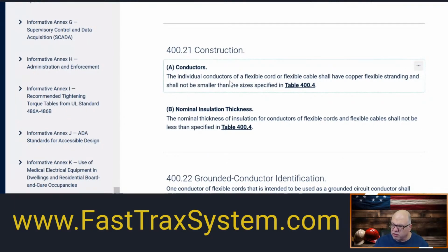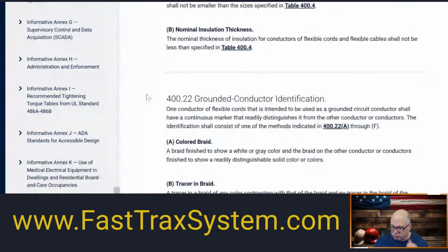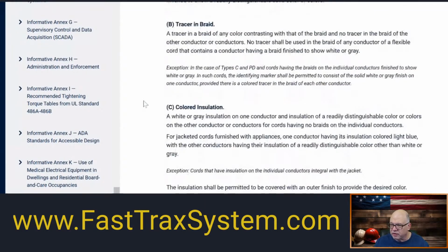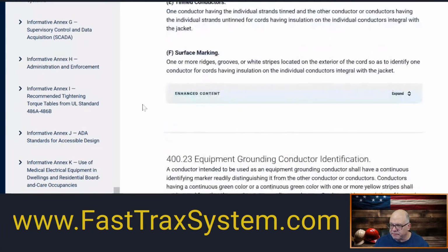It says the individual conductors of a flexible cord cable shall have copper flexible stranding and shall not be smaller than the size specified in table 400.4. Okay, that's stranding, looks stranded. Looks like that is one. I didn't see any reference to 12 in there. So let's keep looking quickly.